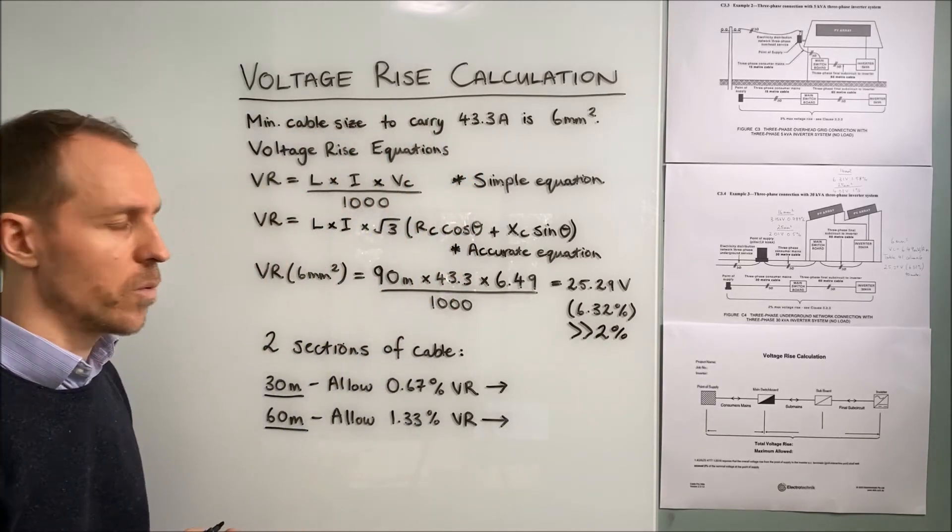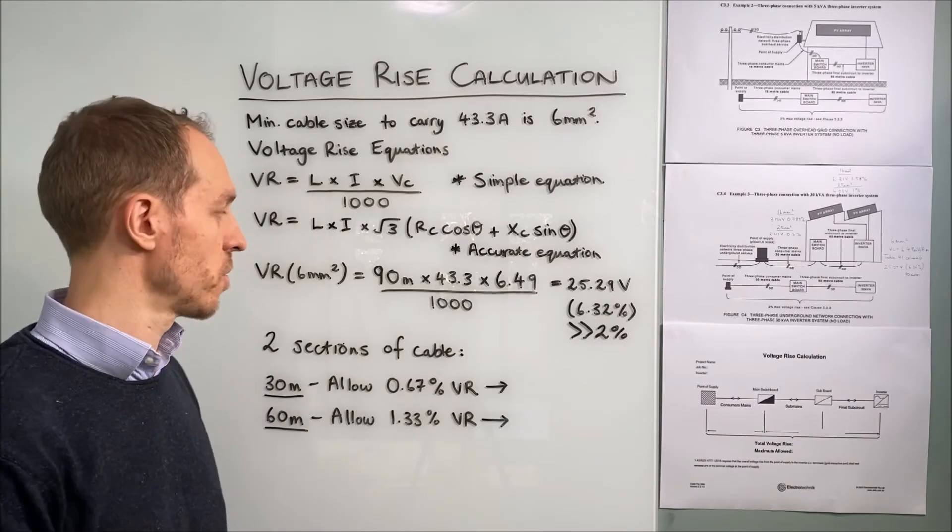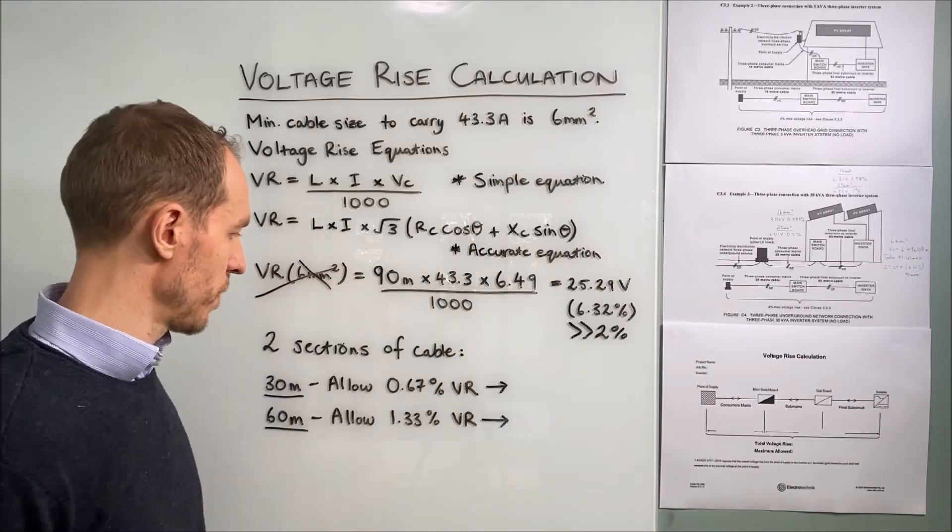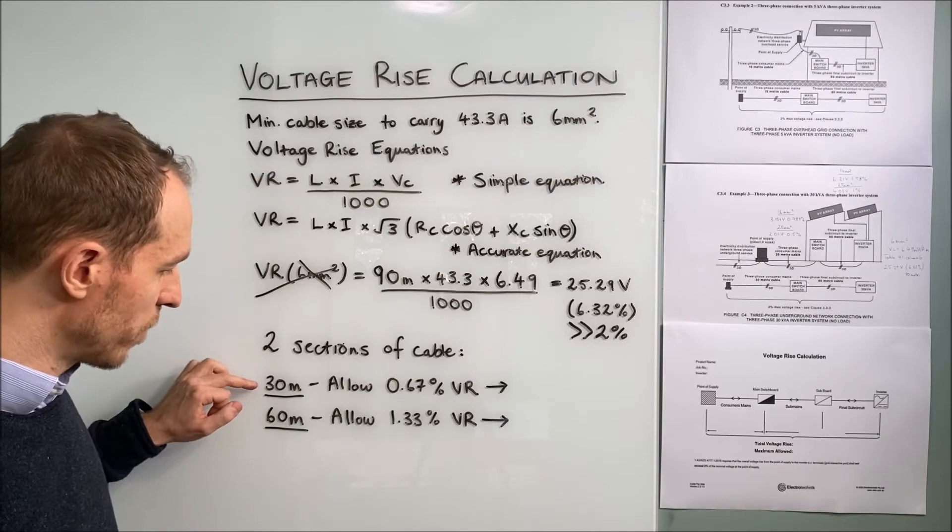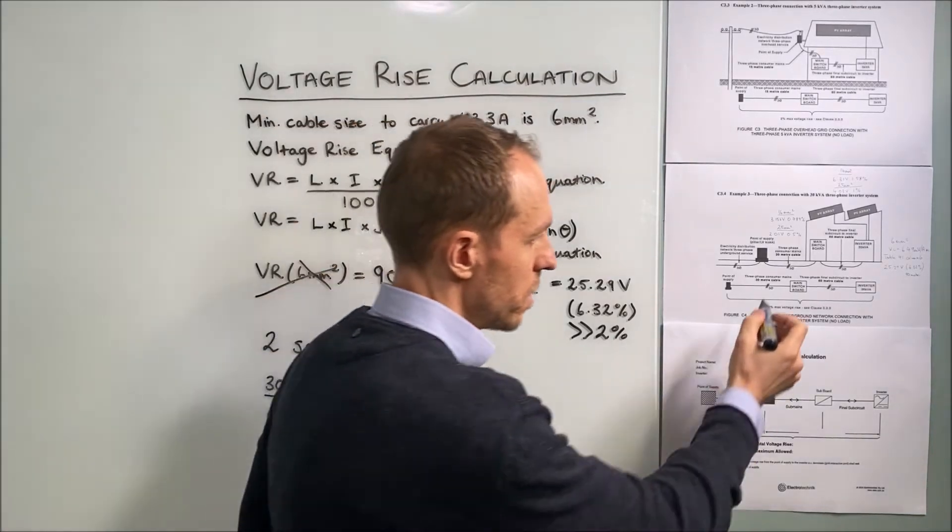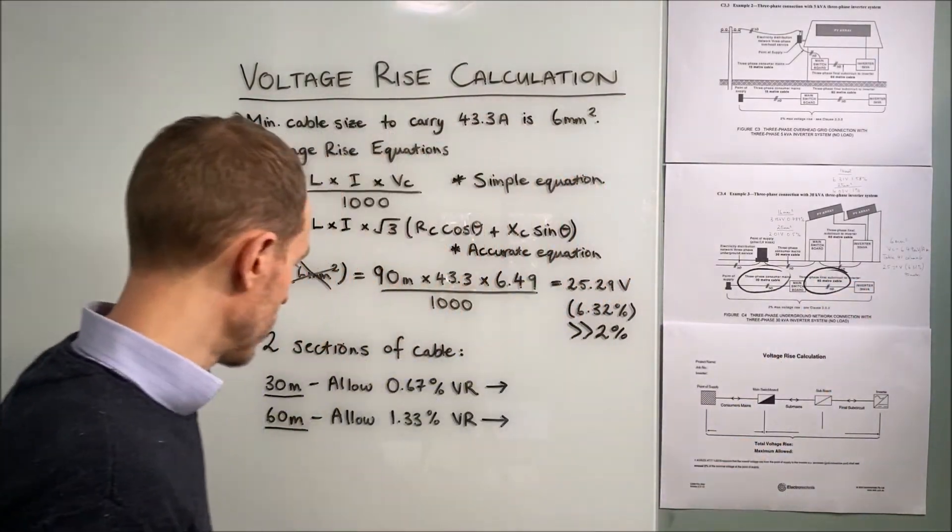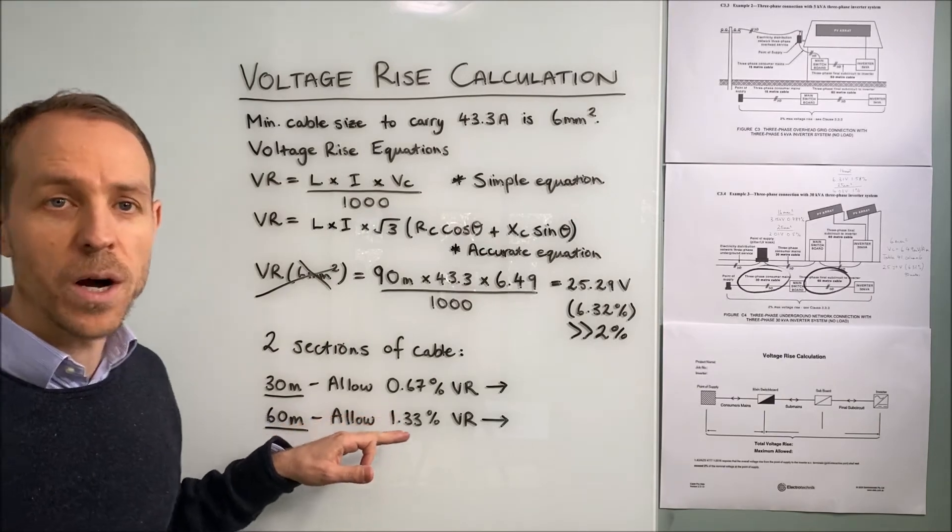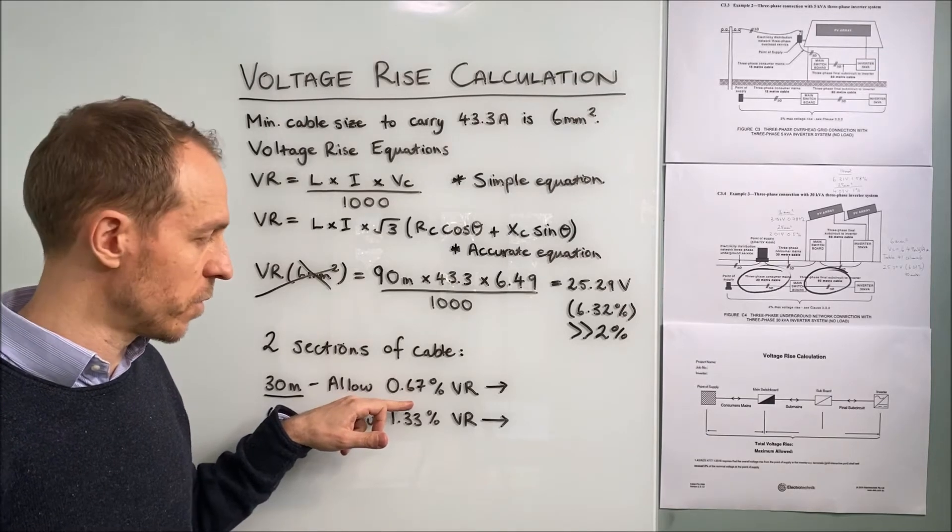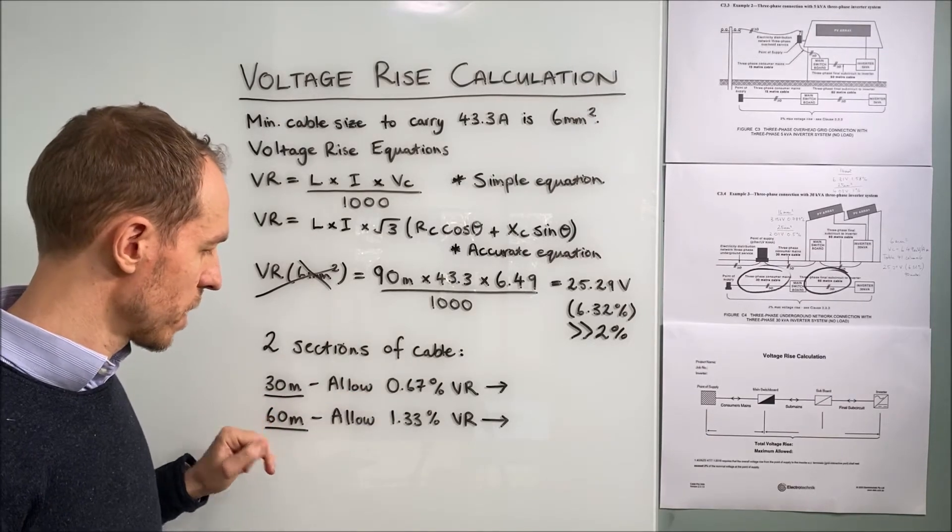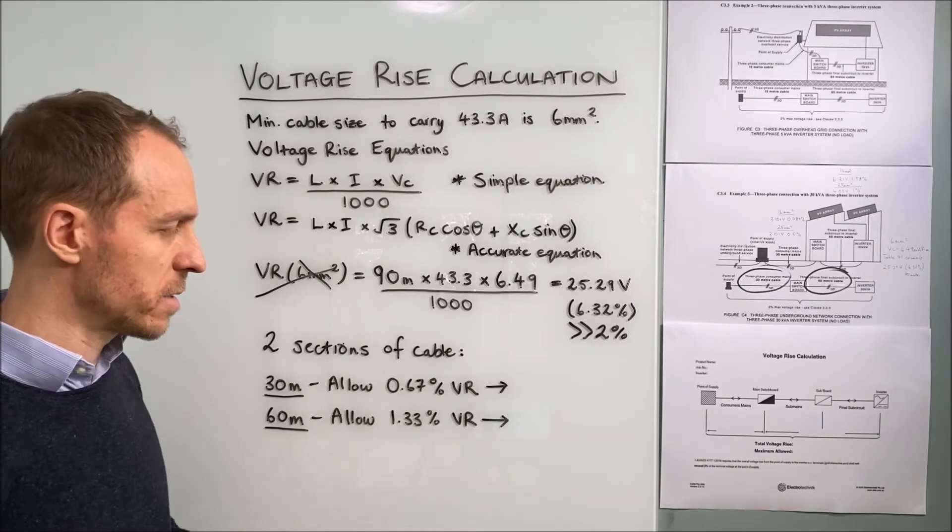So we know we must use a cable size to meet voltage rise requirements which is much greater than 6 square millimeters. We can't use 6 square millimeters. So we'll work it out based on the two sections. Again we've got a 30 meter section and a 60 meter section of cable. So if we divide our 2% up we can allow 0.67% voltage rise for the first section and 1.33% voltage rise for the 60 meter section.